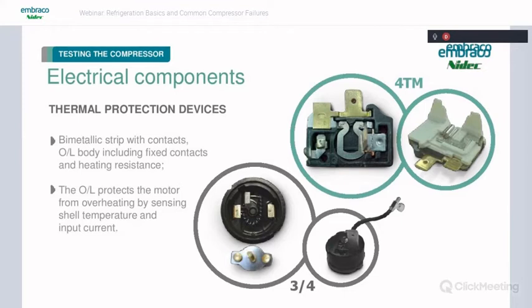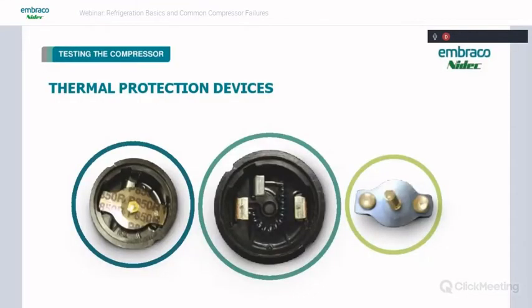The 4TM kind of works on the same principle, but it's a more compact overload device. This is the heater here, and you actually have the same little bimetal with contacts on it that deflects. It's just very compact. It's almost flat. But these are the two types of overload devices you'll see on our small hermetic compressors. And this is a look inside the 3/4 round. You can see the bimetal with the contacts on it and the contact surface here, and you can see the little heater wire in it.